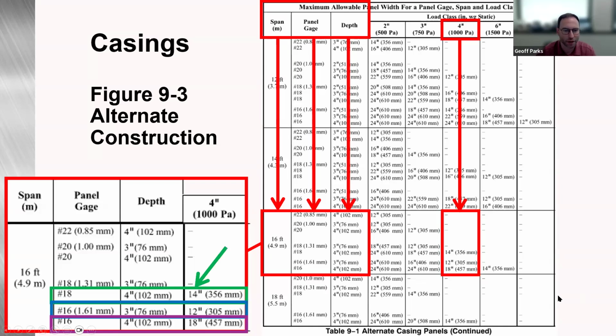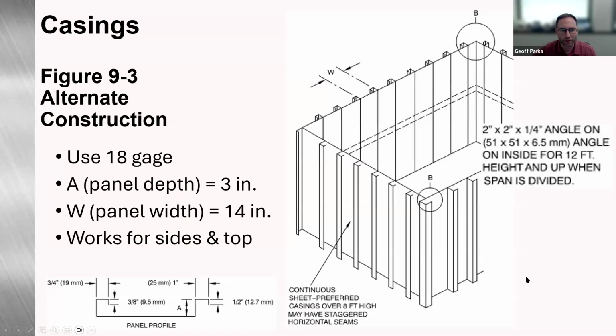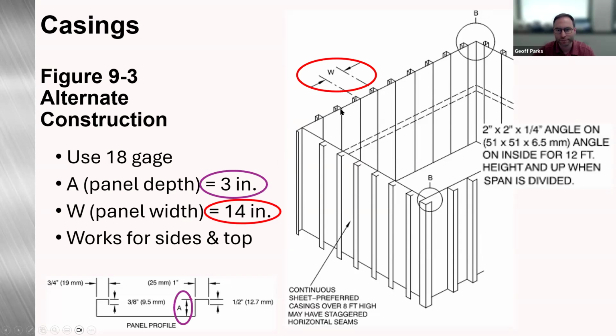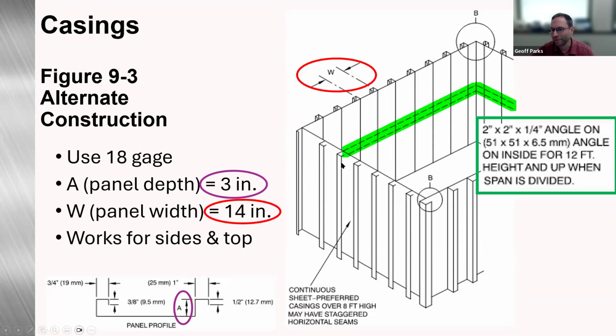If we look at the top one a little closer, back on figure 9-3, we're going to use 18 gauge. Our panel depth is going to be 3 inches. That's our A dimension. Our panel width is going to be 14 inches. That's the width of the panel shown here. Again, this works for the sides and tops. If we have any height span greater than 12 feet, which we would have on this one because we were building it 16 feet, we would need to use 2x2 by quarter angle to divide the span. And down here, continuous sheet would be preferred for casings over 8 feet high. You may want to have staggered horizontal seams.